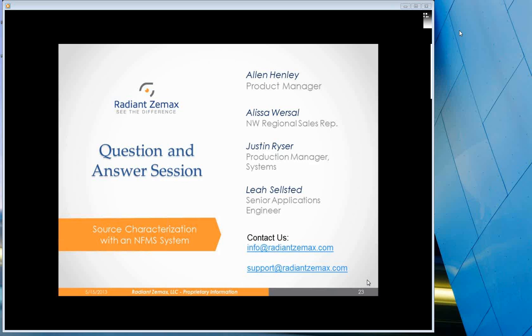Sure. So the parameters that are actually measured are luminance and color. And then we use that database of luminance and color measurements to interpolate and sample into an intensity distribution. So in the end, you get the near field and far field distribution of intensity and color. So what units, for example, would we be measuring in? So the end product is in candela. The original camera measurements, the database of measurements, are in candela per meter squared, which is luminance.